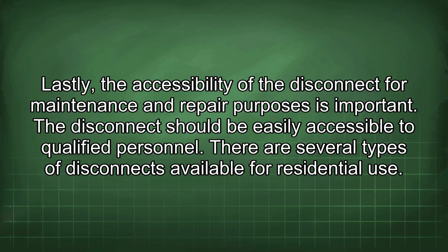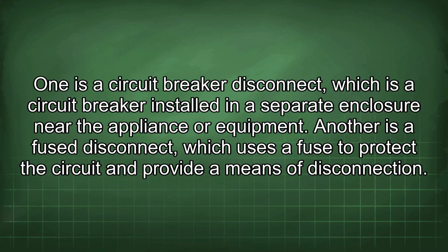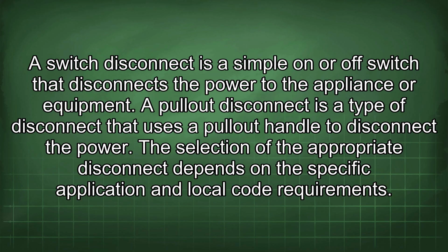There are several types of disconnects available for residential use. One is a circuit breaker disconnect, which is a circuit breaker installed in a separate enclosure near the appliance or equipment. Another is a fuse disconnect, which uses a fuse to protect the circuit and provide a means of disconnection. A switch disconnect is a simple on or off switch that disconnects the power to the appliance or equipment. A pull-out disconnect is a type of disconnect that uses a pull-out handle to disconnect the power. The selection of the appropriate disconnect depends on the specific application and local code requirements.